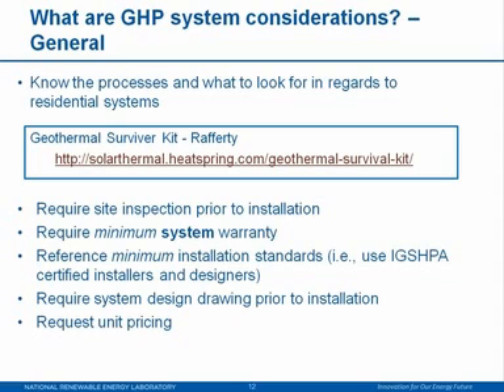Look at the site prior to installation, and require a minimum system warranty. A common problem with ground source heat pumps is that the heat pump unit is usually manufactured by a well-known entity and may have a defined warranty, but you really want to make sure the whole system—the loop field, the heat pump, the distribution system—all works together and functions properly. So you want a system warranty.